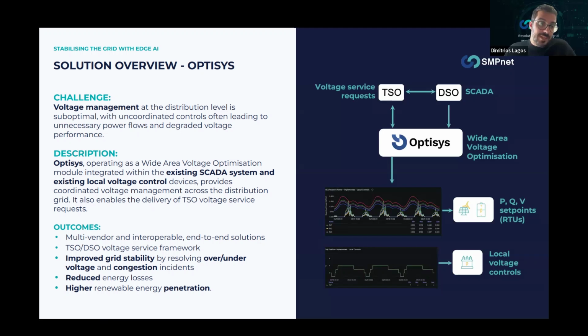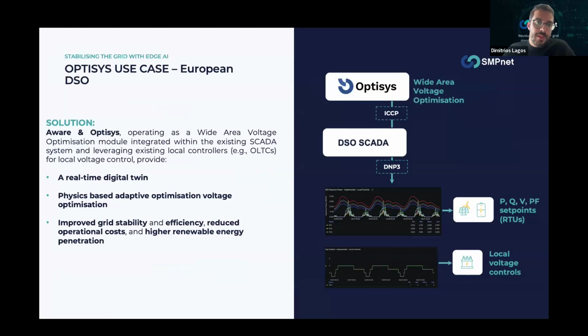TSO-DSO can provide TSO-DSO voltage service. It can improve the grid stability by resolving over and under voltage issues and congestion incidents, reduce the energy losses in the system, improving the efficiency in operation, and increase the renewable energy penetration. So at the moment, we have a use case on a European DSO where the Optisys is utilized for a wide area voltage optimization, and is integrated with the SCADA system.